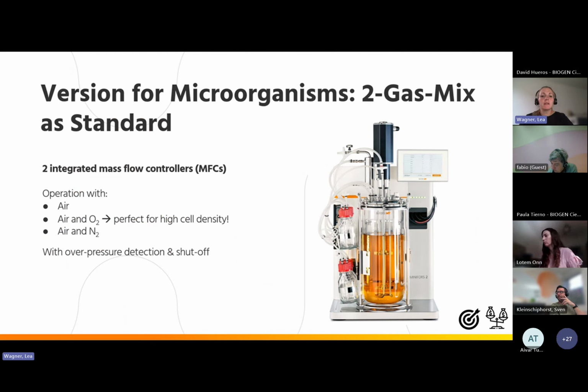So the version for microorganisms has a 2 gas mix as a standard. So there are two mass flow controllers, 2 MFCs, integrated, and the customer has the choice to operate it either with only air, or with air and oxygen, which is perfect for high cell density because if there are more cells, you need more oxygen. You can increase the oxygen content inside the media by increasing, for example, the gas mix. And there's also the option to operate it with air and nitrogen, which is not that often, and it's for anaerobic processes, so for microorganisms that do not need any oxygen.